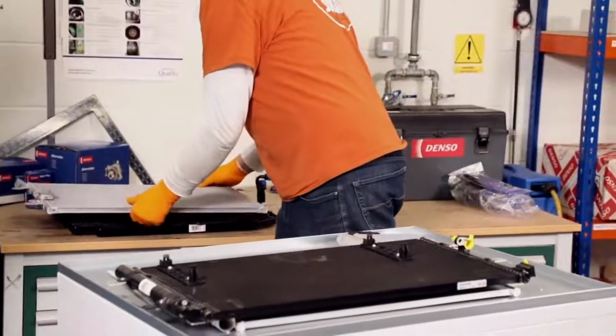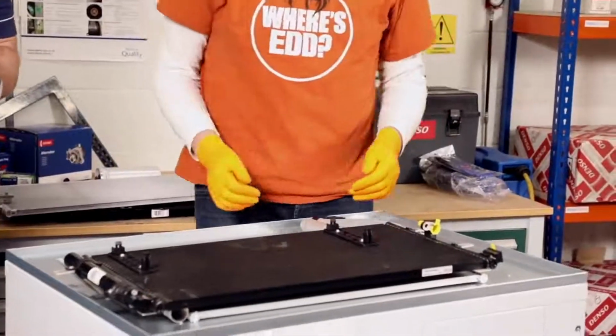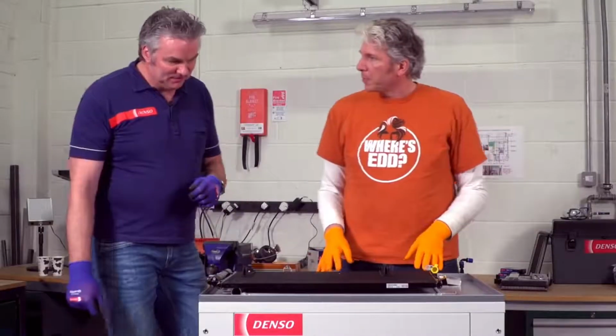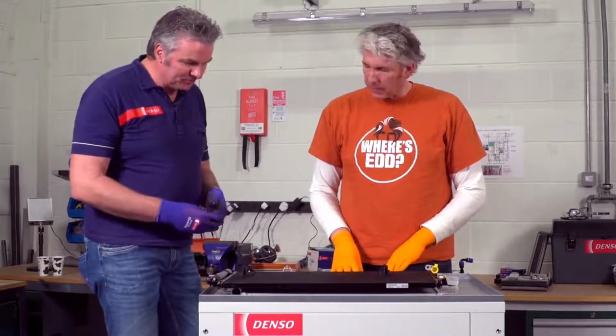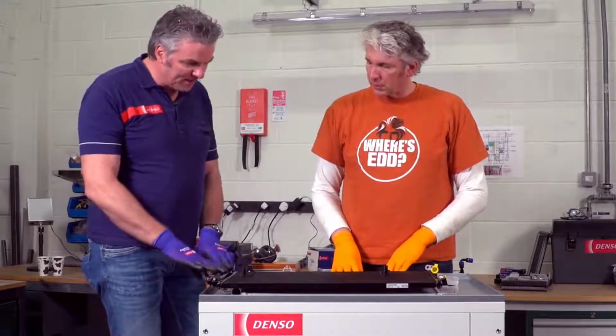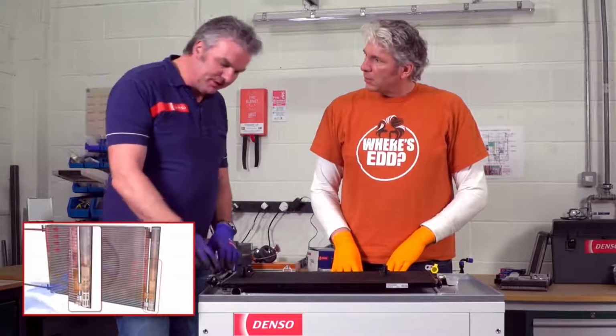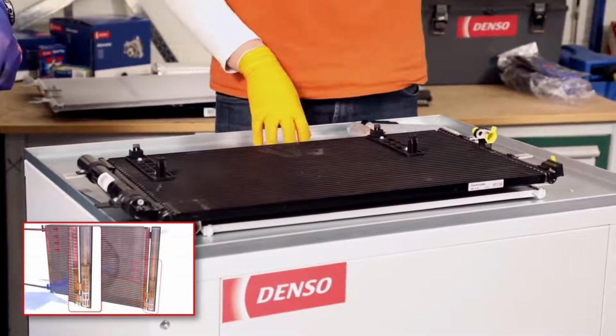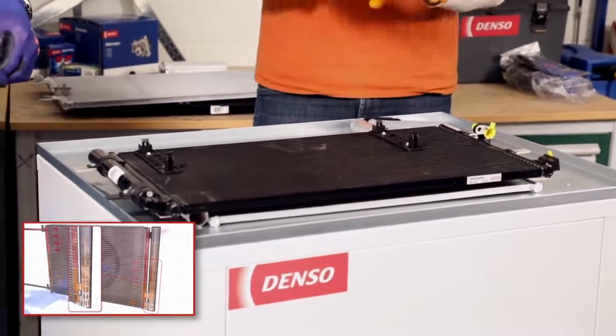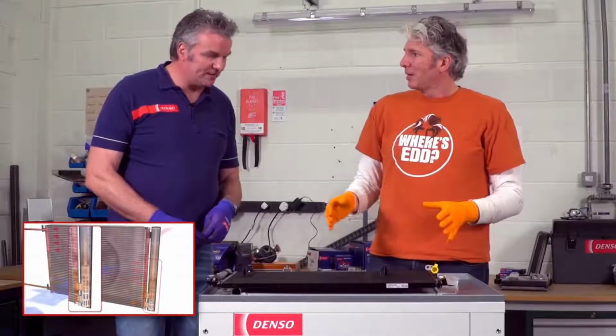So we're moving on from there. We now come to something which is much more modern. So this is still a parallel flow or multi-flow type condenser, but this one we call a subcool condenser because it has an additional heat exchanger in the lower part of the condenser. Okay, so there's cool, which is what those are. This is subcool, so below that. So it's actually lowering the temperature of the refrigerant, exactly.